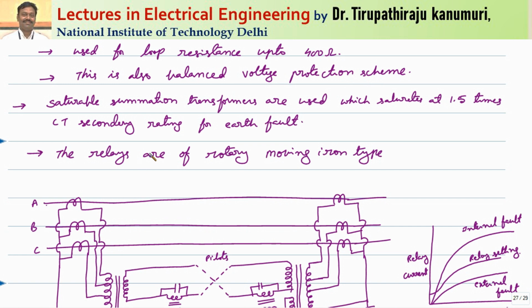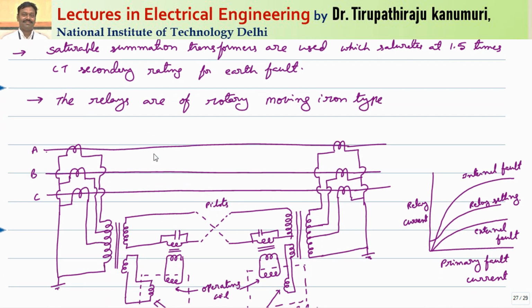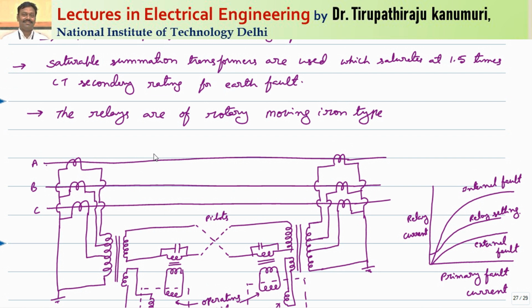Here also a summation transformer is used, similar to the winding in the translay scheme. This summation transformer has three terminals. A phase is connected here, B phase is connected here, C phase is connected here. The current through this one will be IA, this one IB, and this one IC. Whenever a phase fault comes, the current passes between two phases, like A and B, or A and C, or B and C.